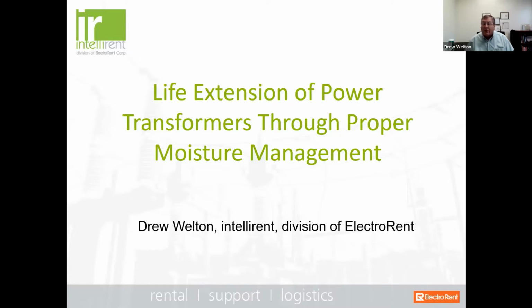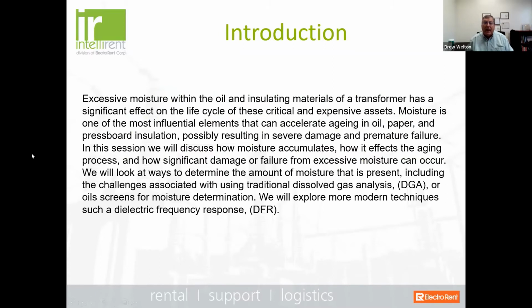And the problem is between the time you have to order a new transformer because your asset is aging out, you just don't know what's in store. The average transformer in the US now is about 38 years old, with 70% of those transformers being older than 25 years. And that is well beyond the life expectancy of their original manufacturing. So one of the things I think is most important is that we do everything we can to try and maintain these critical assets, either before ordering a new one or, at this point, some of the manufacturers aren't even taking orders. It's getting so bad. So we're in a very difficult situation.